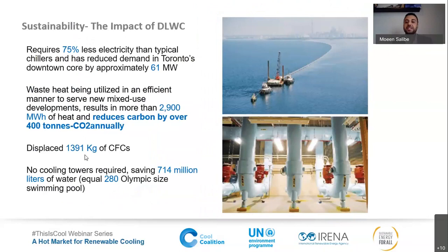This is the impact, shown in the picture on the top right—a real picture when they put 9 miles of pipes into Lake Ontario. It was a massive project, costing approximately $300 million. It requires 75% less power than conventional chillers using pumping. That saves the city approximately 61 megawatts of electricity versus installing mechanical chillers, and reduces emissions by approximately 400 tons of CO2 annually. We displaced 1,391 kilograms of refrigerant by not using chillers. What an amazing system, addressing all the points for renewable cooling and reducing emissions.